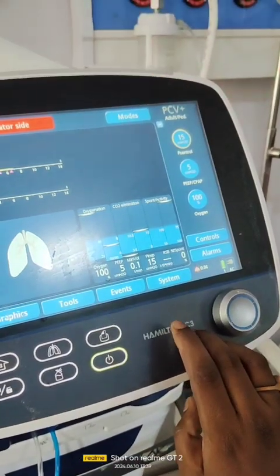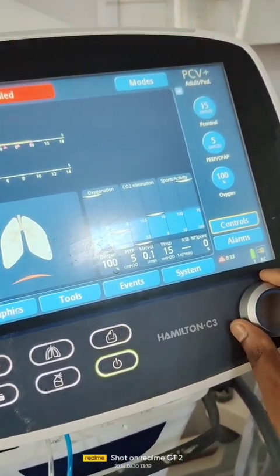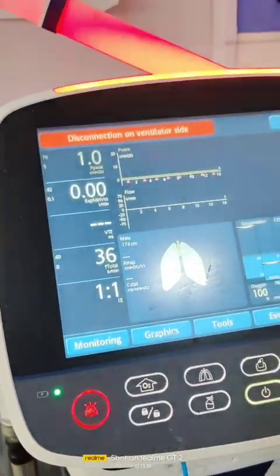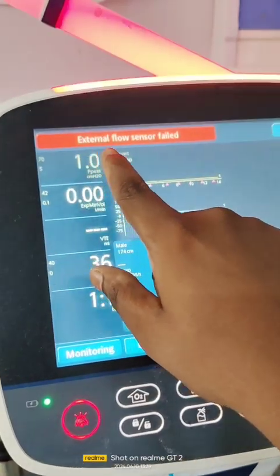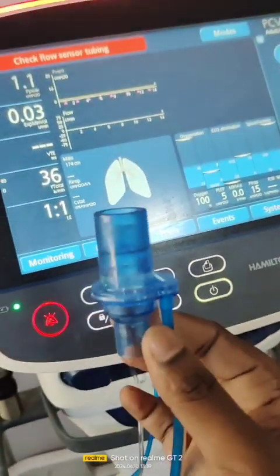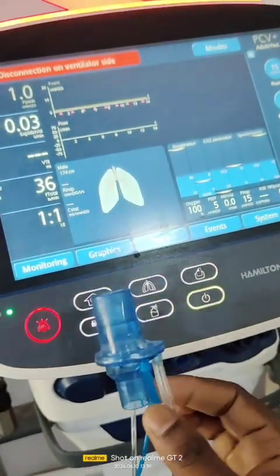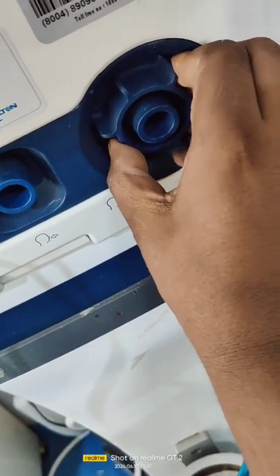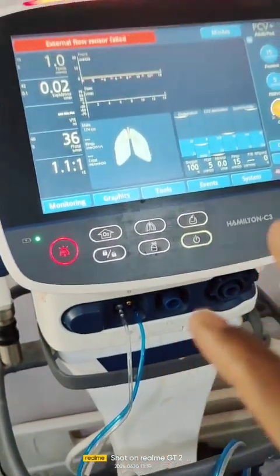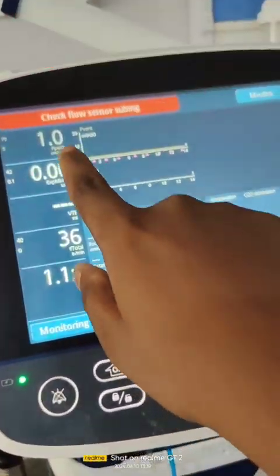So whether the machine is working or not, we have to check all things, and calibration and auto calibration. By using the test lung we have to test pass also. Okay, so these are all done. If any error is coming, external flow sensor failed, because we didn't attach the flow sensor to this patient circuit. Okay, so like one by one, and here also see, you can hear these are the valves. You have to open and close them, and you have to check all these things, and these are external parts. You have to check the equipment details, okay, and physically. And if there is any leaking test, then we have to check just this one. Okay, now getting an alarm, because we didn't connect the flow sensor and the tubing is not connected, so that's why the message.